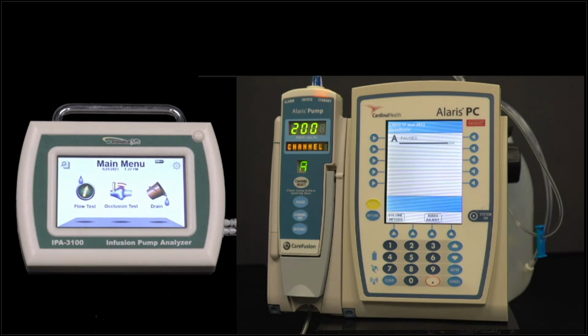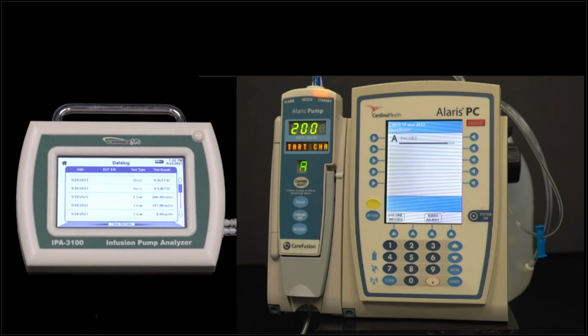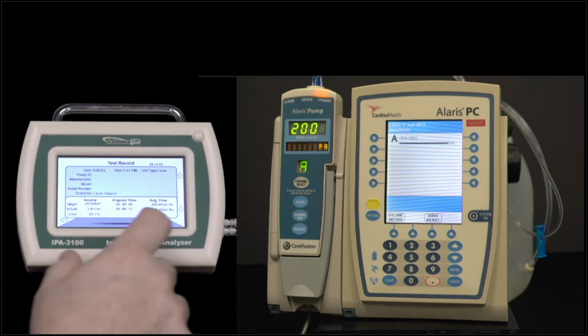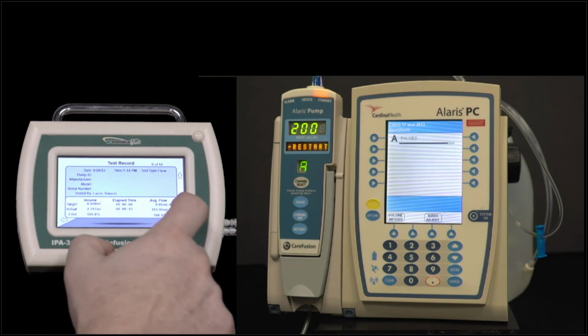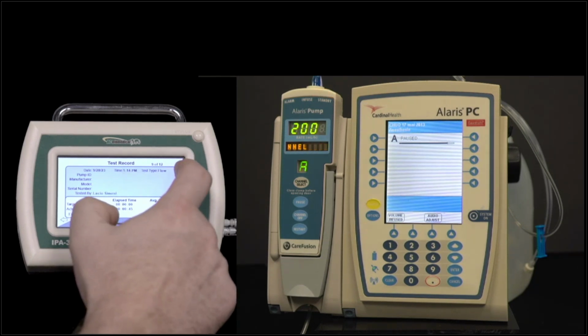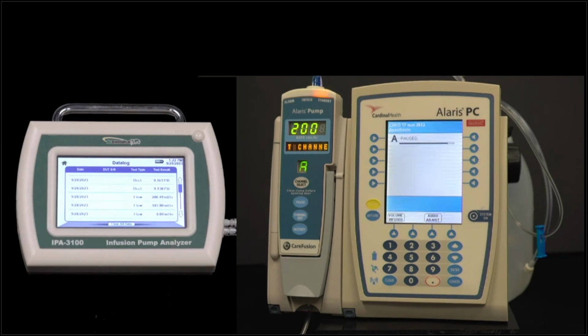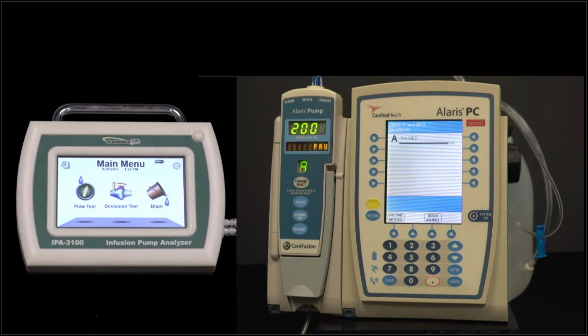So then we go back to our home screen. If we want to see the data we've collected, we've got a history of all those tests right here. This shows that flow test we ran. Again, if we entered information, it would show here about the infusion pump we're testing, giving you the settings as well as the measurements. We can scroll through all of our test records if we want. Those are all the onboard test records available on the unit.